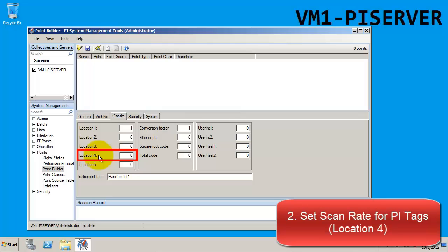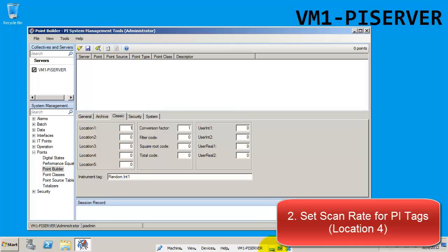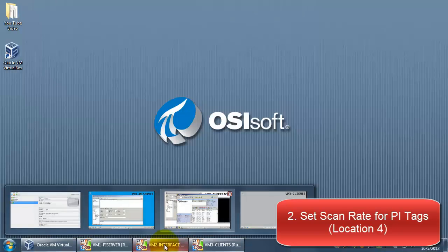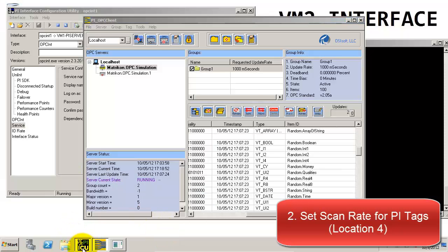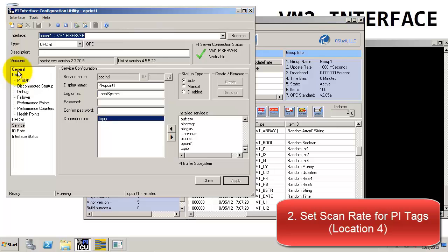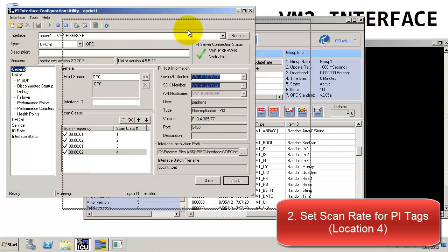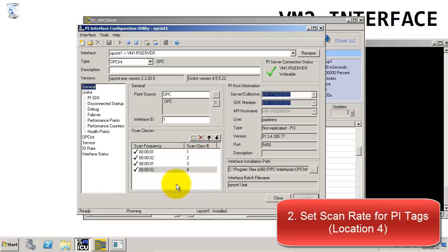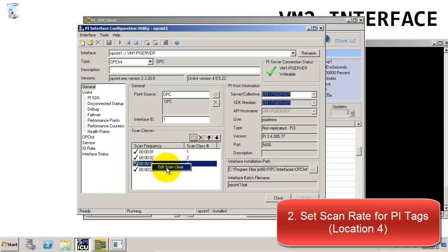Location 4 is used for this interface to designate which scan class to use. If you recall, back on the OPC node in the ICU, we have several scan classes listed. Let's go back to that node. Looking at the ICU under the general tab, you'll see the scan frequencies and their corresponding scan class number. These scan frequencies can be edited if you right-click and then select edit scan class. Let's change this one to, say, 3 seconds.